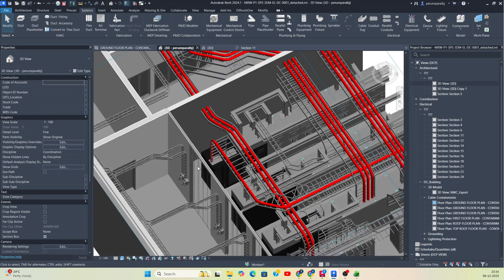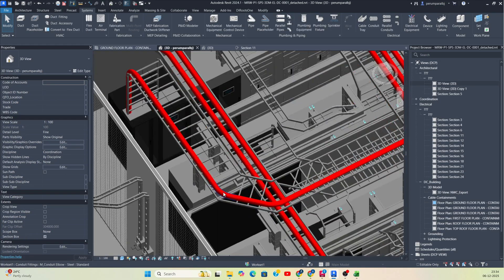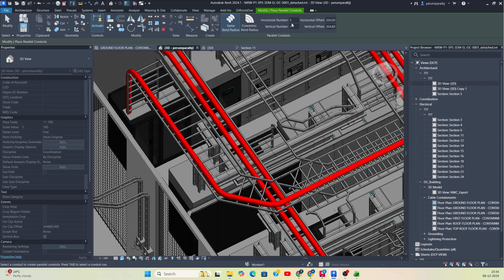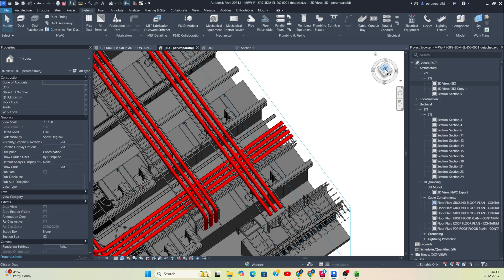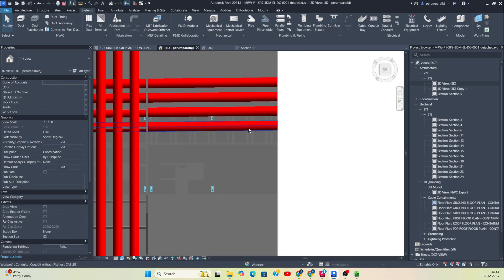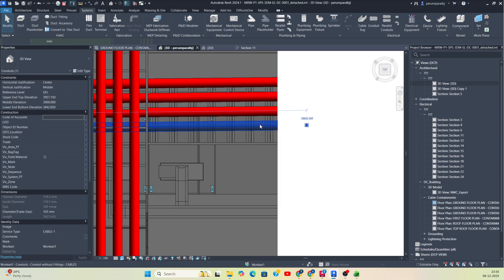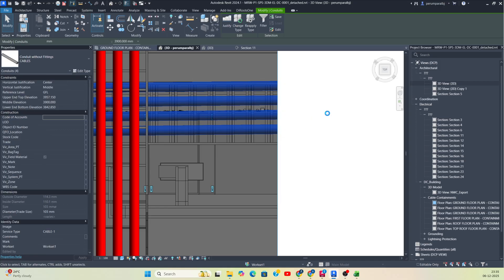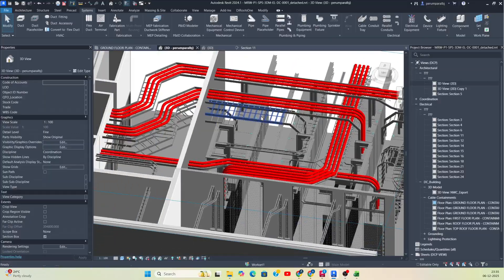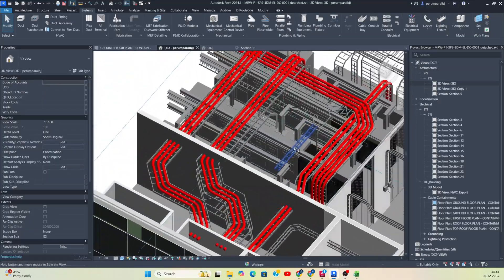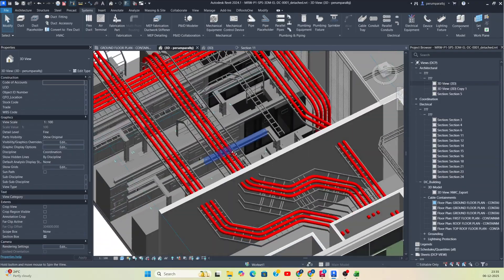Go to the 3D view and select Parallel Conduit. How many numbers do you require? For example, four numbers — make the spacing 175 so it will accommodate all conduits in the tray or ladder. Manually you can adjust the size and spacing — just select the conduit and move it down. It will fix to the cable ladder like this. This is a small exercise for those working in Revit Electrical.